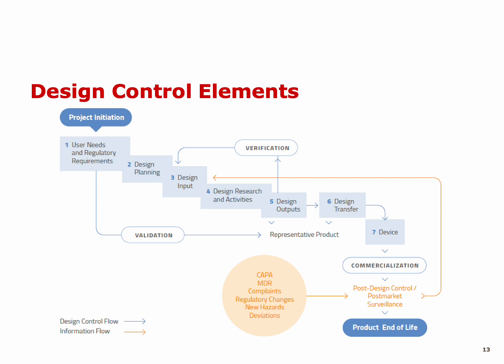But sometimes it may be something that may harm the population. It may also cause some deficiency. So we need to look into each and every complaint, open them, have them reviewed by a subject matter expert, and then close the case. Sometimes the case may end up with a recall of the batch of that medical device.